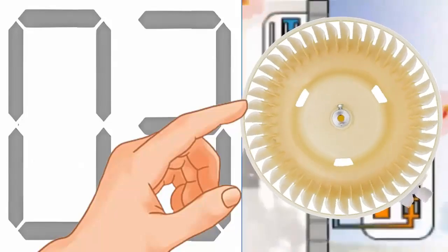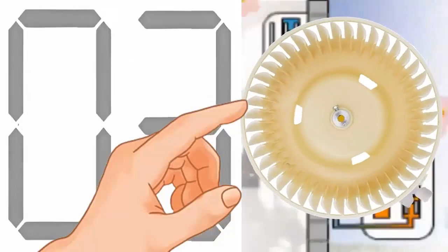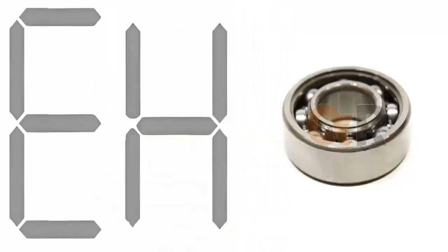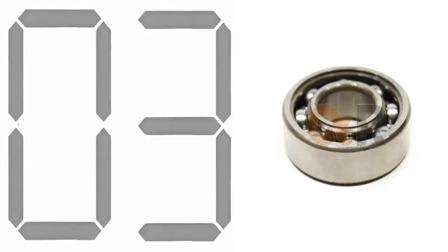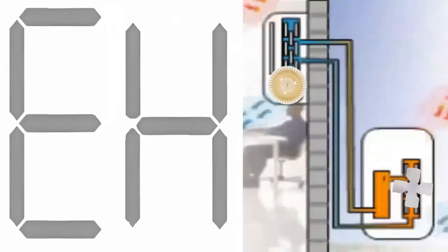2. Check the fan motor. If the blower is difficult to turn, it means that the fan motor is defective and its bearing is stuck. If the blower wheel spins freely, it could be an issue with the circuit board or the feedback connections of the fan motor.